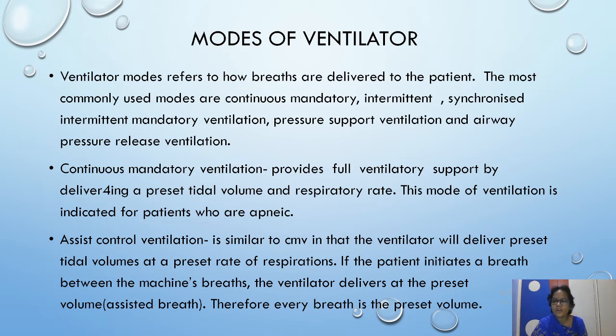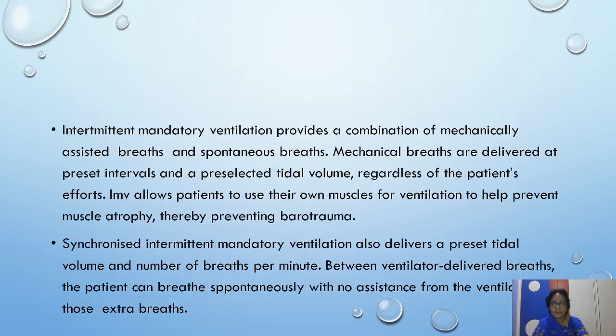Next is the assist control ventilation. It is similar to continuous mandatory ventilation in that the ventilator will deliver preset tidal volumes at a preset rate of respirations. If the patient initiates a breath between the machine's breaths, the ventilator delivers the preset volume. Therefore, every breath is the preset volume in assist control ventilation. If the patient is able to take breaths in between the machine's breaths, the ventilator will still deliver the preset volume.